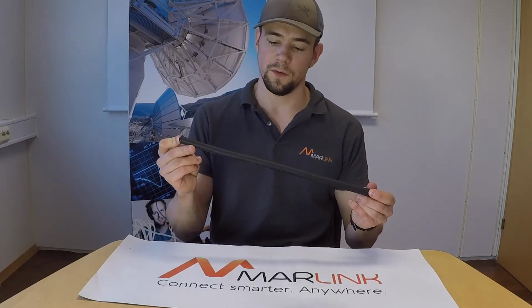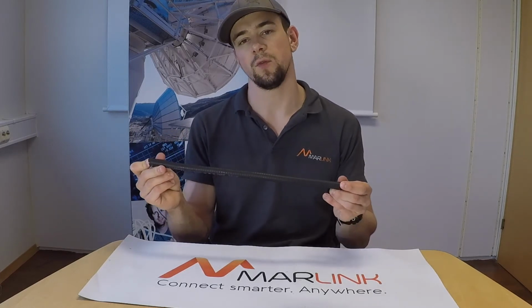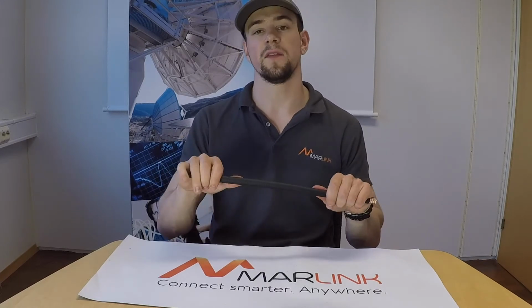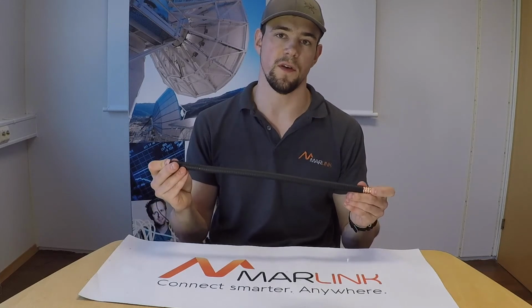In this instructional video, I'm going to show you how to properly prepare and terminate the new standard low loss cable for Marlink. Our new standard low loss coax cable is the Cellflex LCF12 and it is more stiff and provides a lower degree of loss than the Cellflex SCF12.